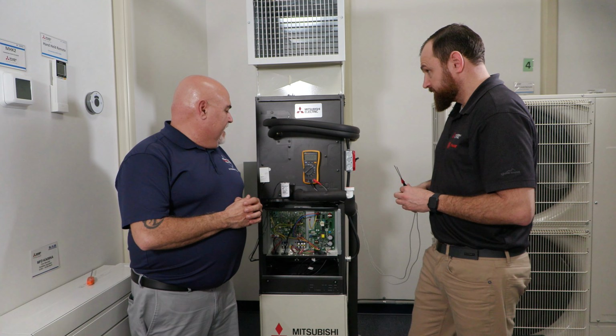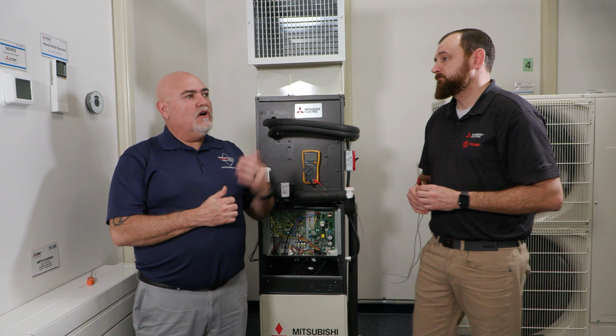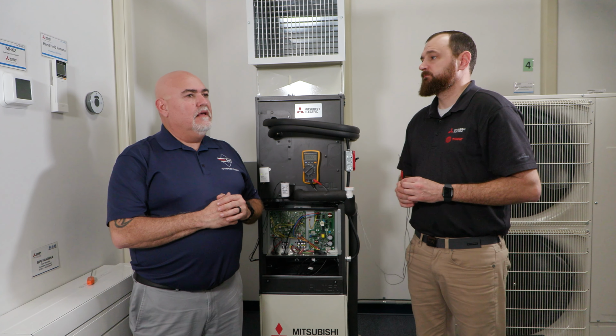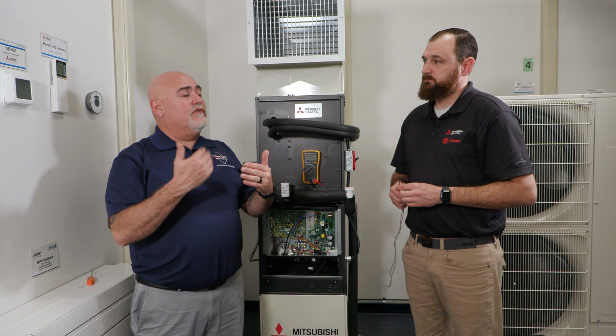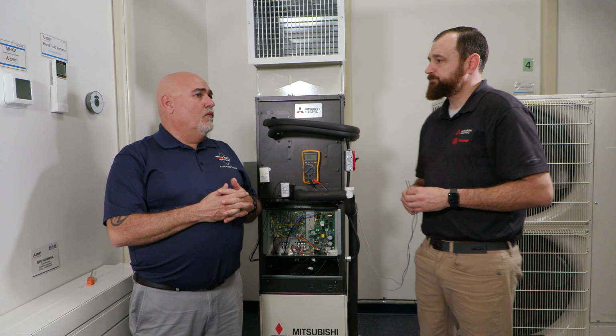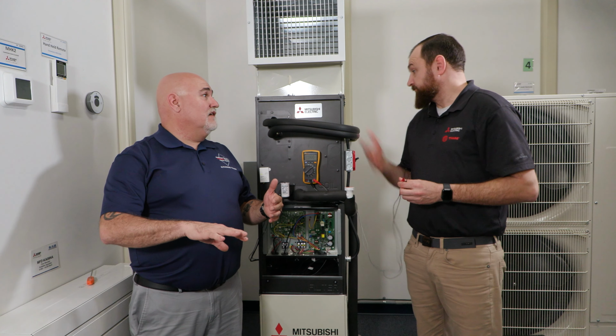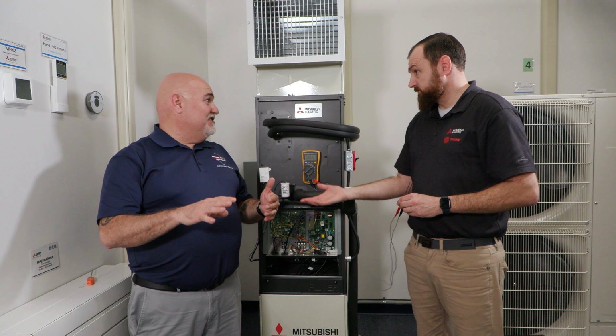So again, we have to rule out what caused this rotational feedback. Basically, the system does not see, or the indoor board does not see a rotational feedback voltage coming back to it. That's what throws the error code. Okay. So where are we going to start? We got to rule out the most obvious. Right. Blower wheel? I mean, is that seized? Seized. Okay. Right. The motor is seized.